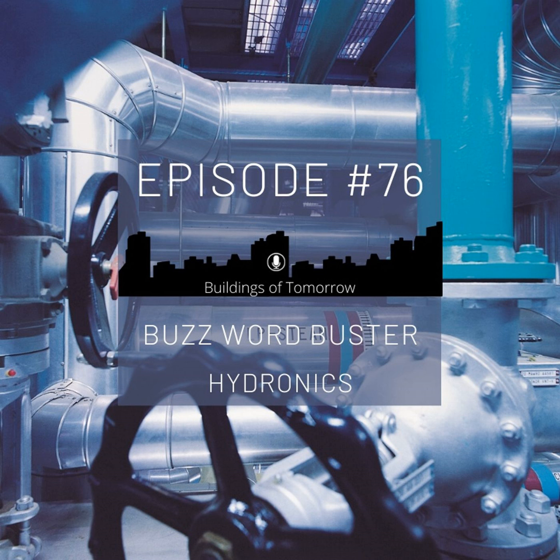If the pump puts less pressure on the PICV, it basically defaults back to a standard, normal, or KVS valve. And then you lose the benefits of this independence of the pressure situation surrounding the valve. Right. So the delta P min is the minimum system pressure that has to be applied at that valve at that point in the system for it to be able to operate as a pressure independent control valve.